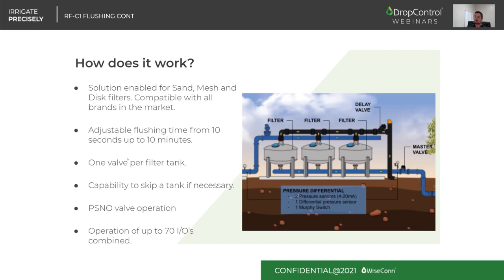You can have one valve per tank or one solenoid per filter tank. You are capable of skipping a tank if necessary. So if you have a filter station that has 6 tanks and one of them needs to go under maintenance, you can change at any time through the website or the mobile app to not flush filter tank 5. So you can disable or enable which tanks will be part of the flushing cycle at any moment.